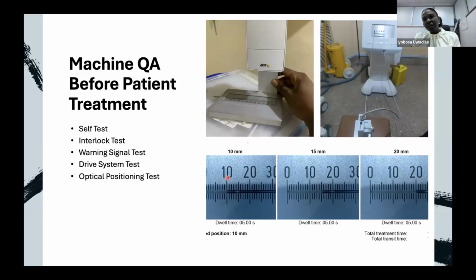During the self-test, the system checks the software integrity, the hardware functionality, the timer, and all that. The interlock test - we check the treatment room door is locking well, the emergency stop button is working, both the physical one and the one on the treatment control panel.